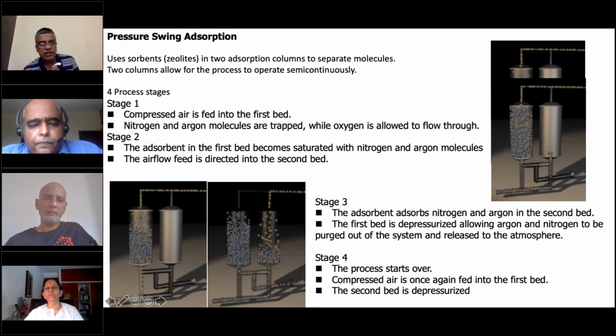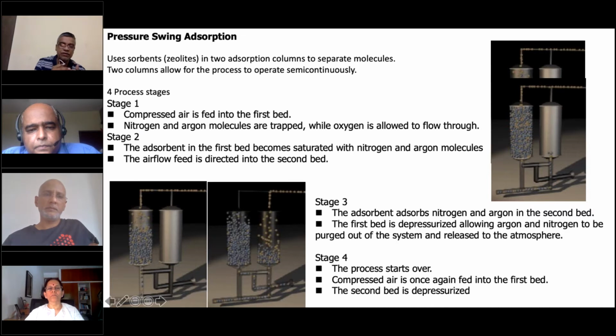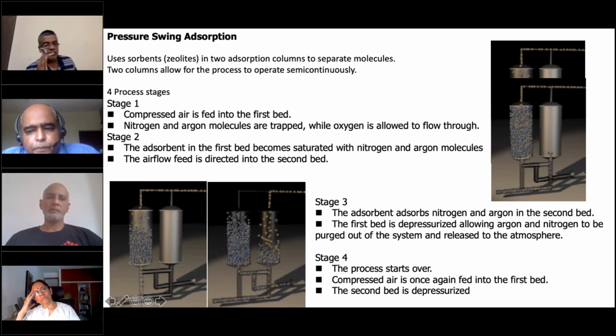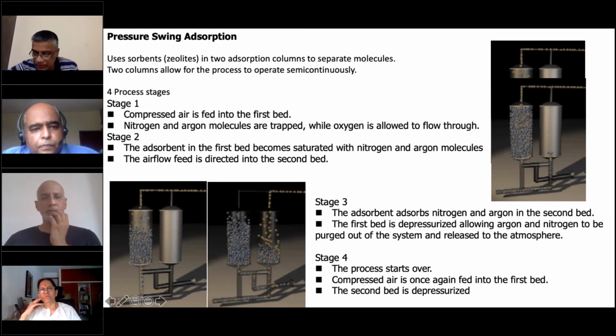This particular bed of zeolite absorbs forcefully only nitrogen and leaves out everything else. So what you are doing is separating nitrogen from everything else, and nitrogen is more than 70%, right? So hence you are separating oxygen. One side you push it, it separates, you open the nitrogen, whatever was separated comes out, oxygen is left behind. While this is happening, the second chamber is opened, and then that is pushed. So you keep swinging the pressure between one chamber and another chamber, so that you separate oxygen sequentially and collect it in one container so that you can give it continuously.